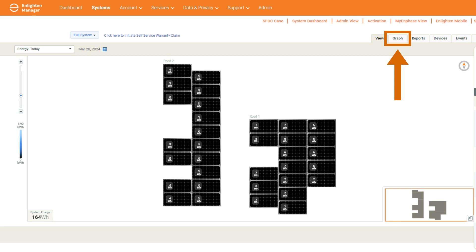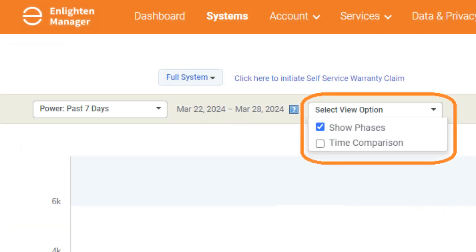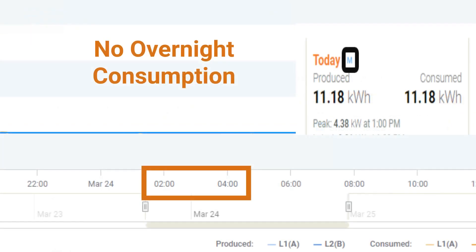If you are not on site, the second option to resolve mirroring with overnight consumption being reflected is to access the installer portal and navigate to the graph view tab. Once in the graph view and you have verified the overnight reporting of consumption, select Show Phases in the Select View dropdown. Doing this will allow you to see both phases of the consumption CTs, which will help you to identify which phase or phases may need to be corrected. For instructions on how to reverse polarity of metering using the installer portal, see the video linked in the description below.